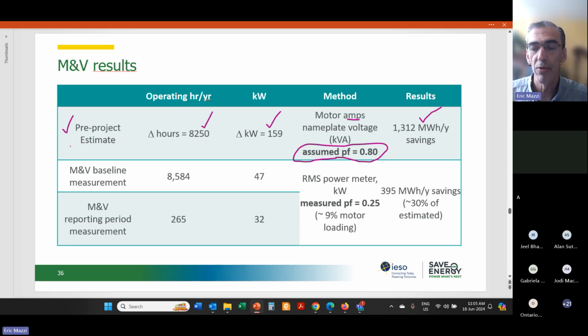An M&V plan was written and included in that incentive agreement. And then baseline measurements were done for about 2 months, and it turned out that that one motor consumed about 47 kilowatts of real power. The plant technical staff had estimated based on spot readings that it consumed 159 kW.